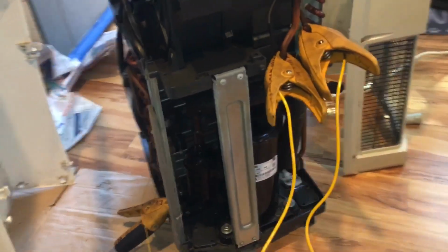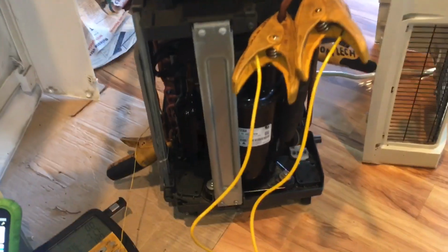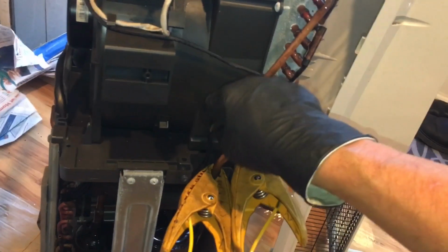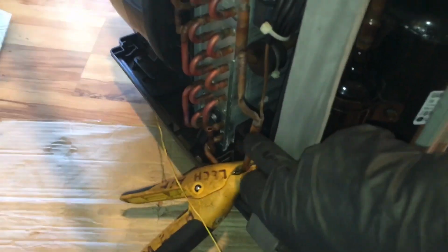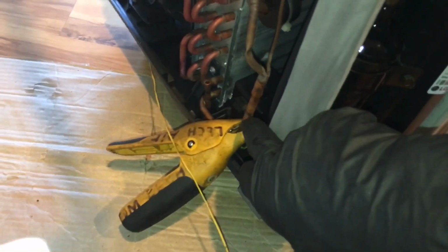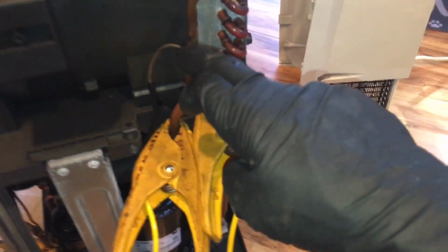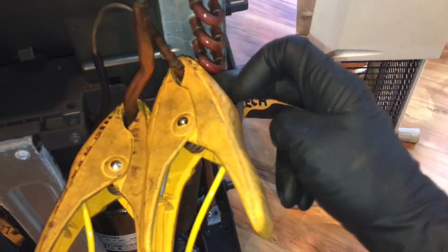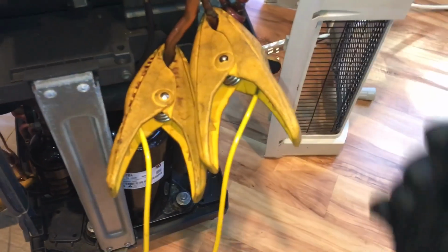Okay, let's get on to the car relationship thing again. So here is a capillary tube that's coming from the bottom of the condenser. This is your high pressure liquid right here, and it's soldered into this little tiny tube. Big tube, high pressure liquid; then it vaporizes through this low pressure little capillary tube right here, as it comes out the end into the evaporator from the condenser. From the condenser to the evaporator. On a car, this would be your orifice tube. Think of it that way.